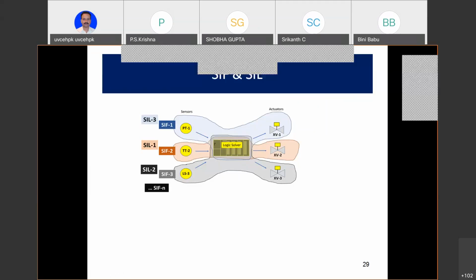Now, a very important point to take away from today's presentation: you've got a transmitter, you've got a PLC, and you've got another transmitter, so 3 items. Now, if you say the first transmitter is SIL 2, the second transmitter is SIL 3, and the PLC is SIL 3, that represents the reliability of that particular unit. But if you go to our little diagram that we drew, and you want to give it a SIL 3 rating, it is all the items put together, after calculating the probability of failure, the summation of this failure, that failure, everything put together. You may be using a manufacturer-approved SIL 3 pressure switch, that's a different matter. But if all of them are assembled, it doesn't mean that if you put SIL 3 items in your factory, the whole factory environment becomes SIL 3.